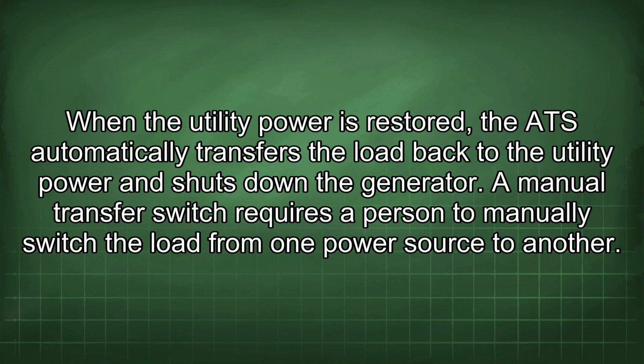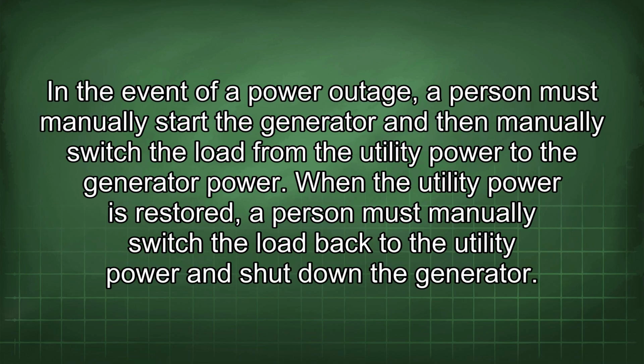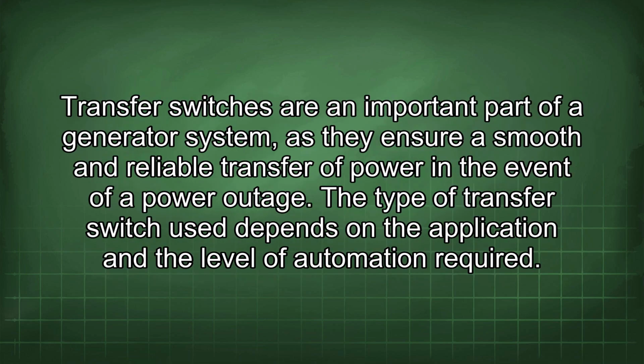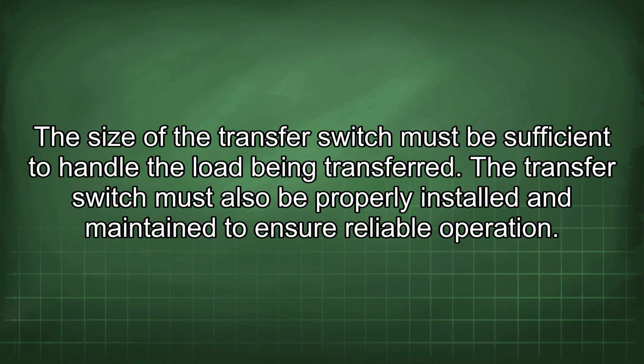down the generator. A manual transfer switch requires a person to manually switch the load from one power source to another. In the event of a power outage, a person must manually start the generator and then manually switch the load from the utility power to the generator power. When the utility power is restored, a person must manually switch the load back to the utility power and shut down the generator. Transfer switches are an important part of a generator system, as they ensure a smooth and reliable transfer of power in the event of a power outage. The type of transfer switch used depends on the application and the level of automation required. The size of the transfer switch must be sufficient to handle the load being transferred. The transfer switch must also be properly installed and maintained to ensure reliable operation.